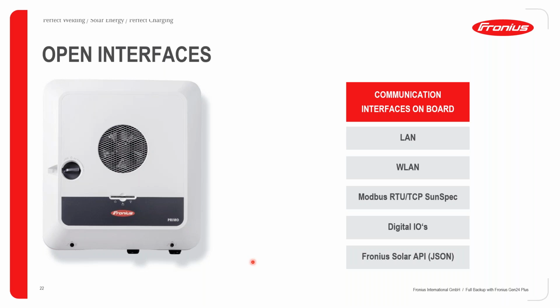This inverter also has Modbus RTU and TCP, so this is very handy when you want to incorporate any third-party device to communicate with the Gen24 Plus. For example, the BYD battery. So the BYD battery will communicate with the Fronius GEN24 Plus over Modbus, okay? And Modbus is also used to communicate with the Fronius smart meter as well.